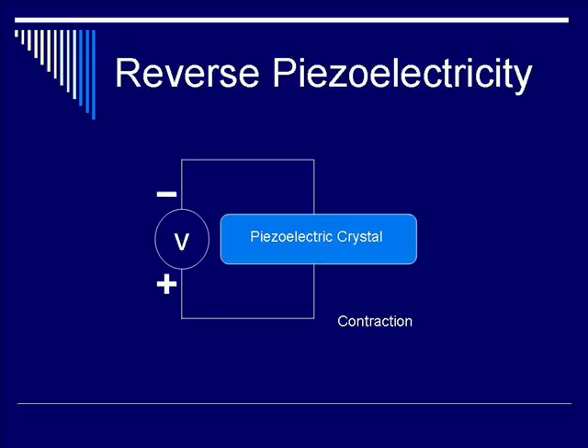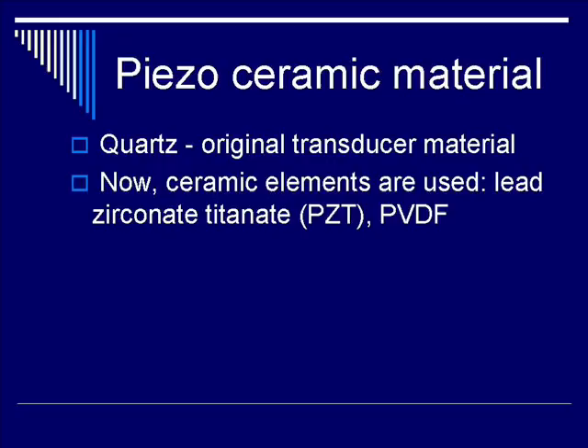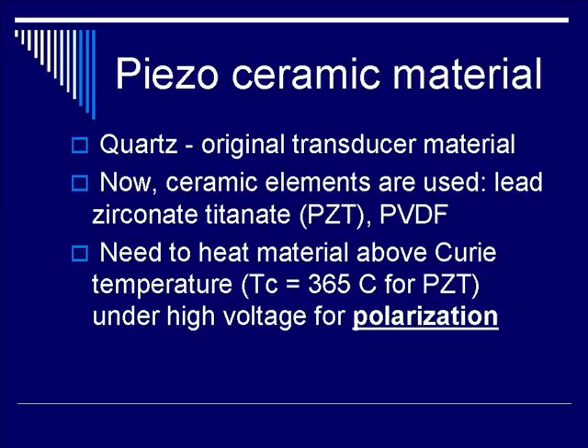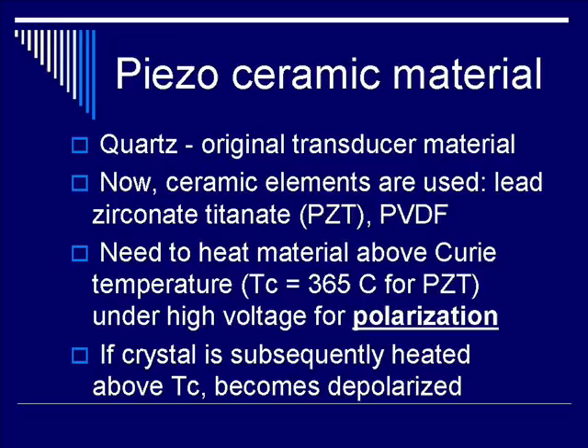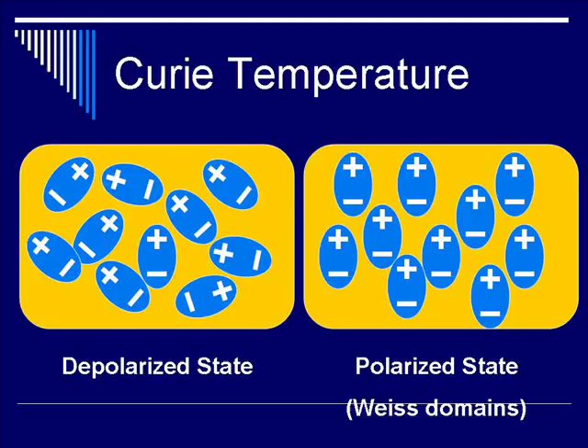This effect is put to great use in diagnostic medical ultrasound. Regarding piezoelectric ceramic materials: originally, quartz was the first material used. More recently, ceramic elements have overtaken quartz, such as lead zirconate titanate (PZT) and PVDF. For both materials, you need to heat them above their characteristic Curie temperature — 365°C for PZT — under high voltage conditions for polarization. If the crystal is subsequently heated above the Curie temperature, it becomes depolarized. Under polarization, all dipole moments are aligned in one direction; in the depolarized state, dipoles are oriented randomly.